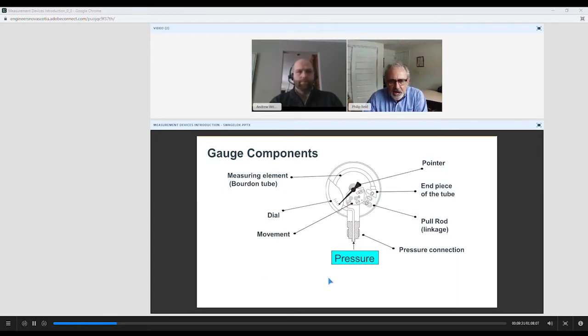So here we have a cutaway of a pressure gauge, and if you were to look into ASME B40.100, you'd see a very similar picture to a couple we're going to refer to here. So we've got pressure coming into the pressure connection, which can be pipe threads, a tube adapter, or many different ways, any type of pressure connection. And as pressure enters, it flows through to the socket. It goes into the Bourdon tube, and the Bourdon tube is a C-shaped tube, and we'll talk a little bit further about this as we move along.